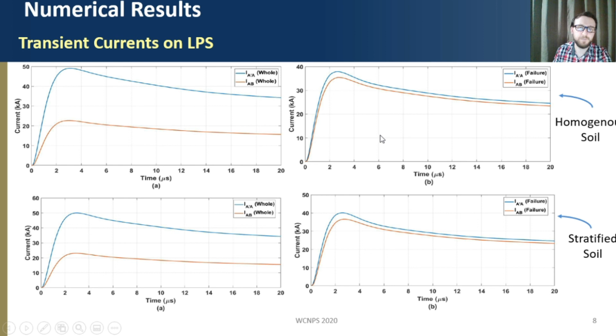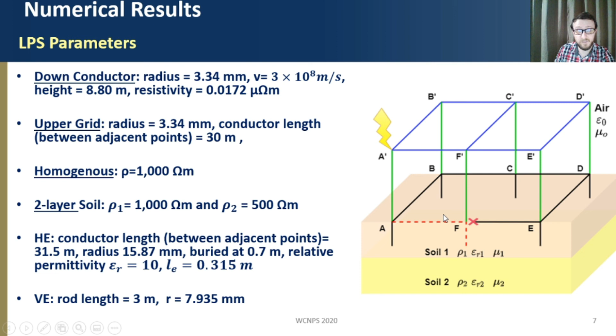Now we are considering the voltage at 5 different points along the grid, so it would be the points A, B, C, D along the ground system grid. So we return here, and in this condition for homogeneous soil, we have almost 900 kilovolts. And here, when we have the rupture, we see for the first case it increases up to 1200 kilovolts. And then when we have the stratified soil, we have lower peaks in comparison with the homogeneous soil. But even so, when we have the damage condition, they present the highest peaks.